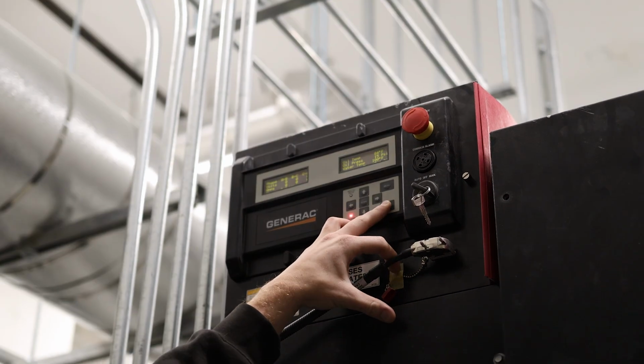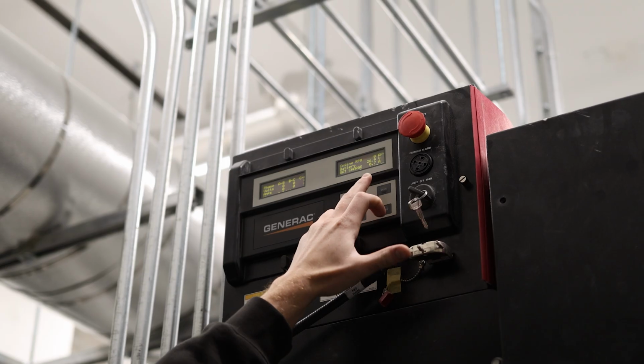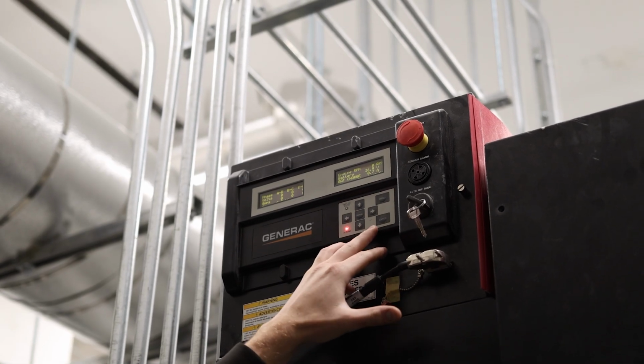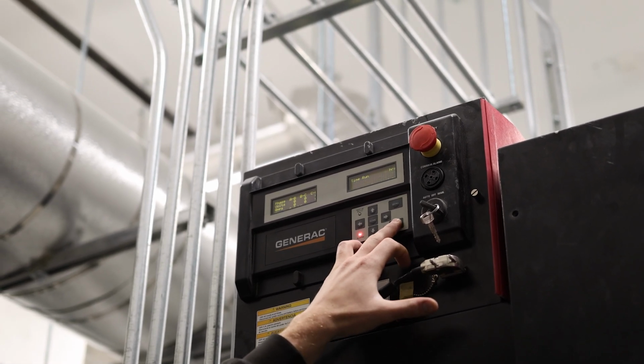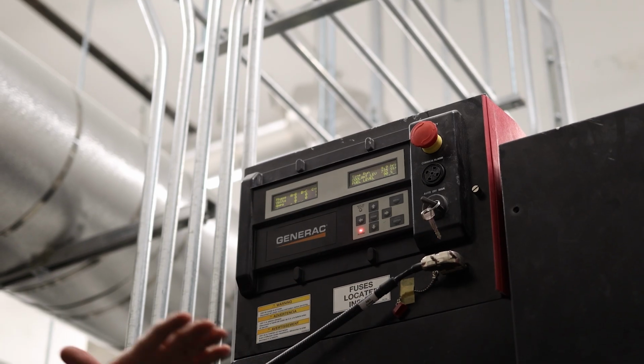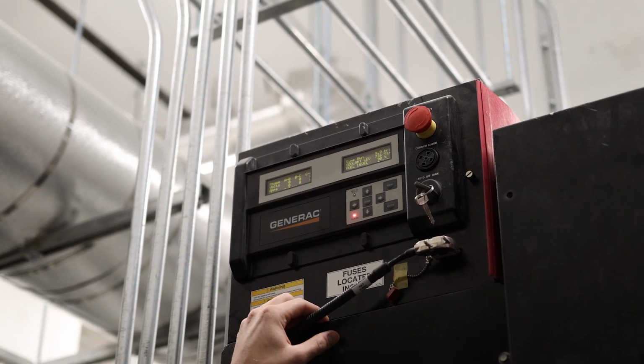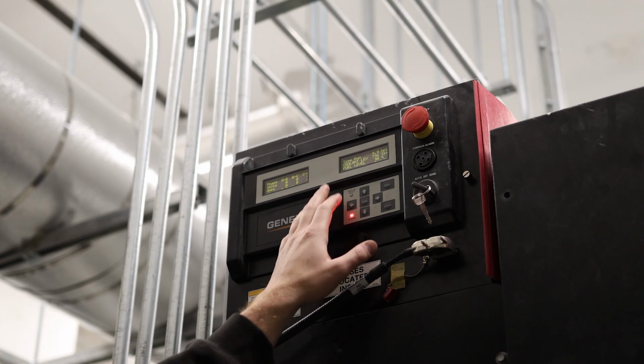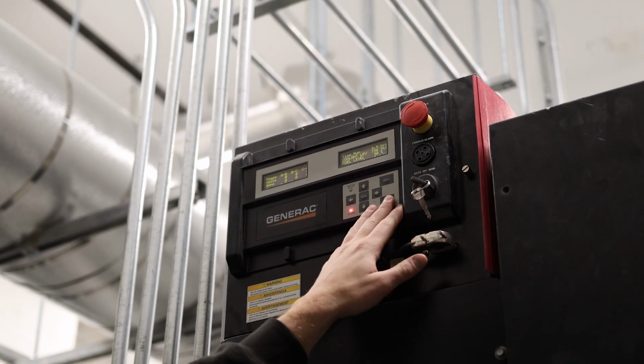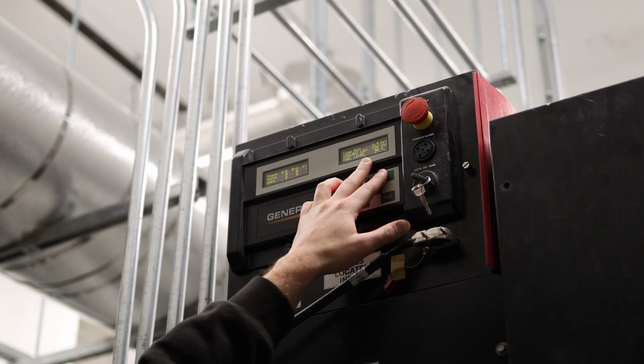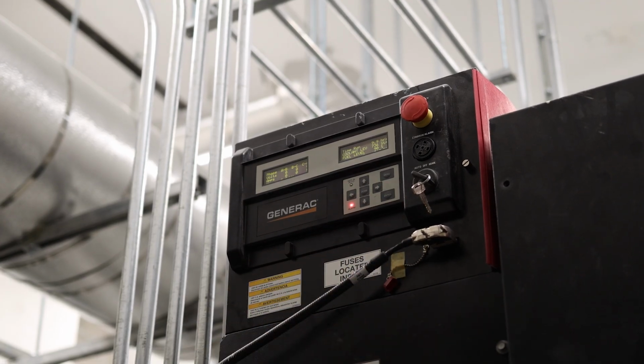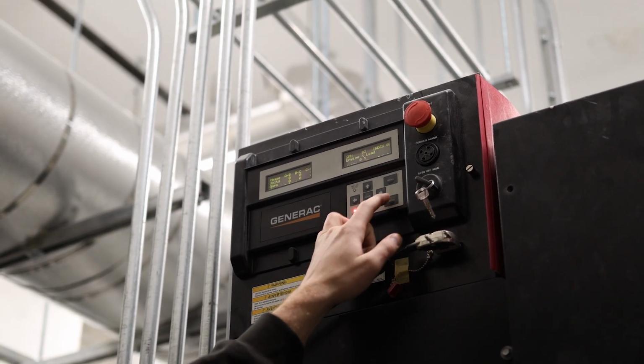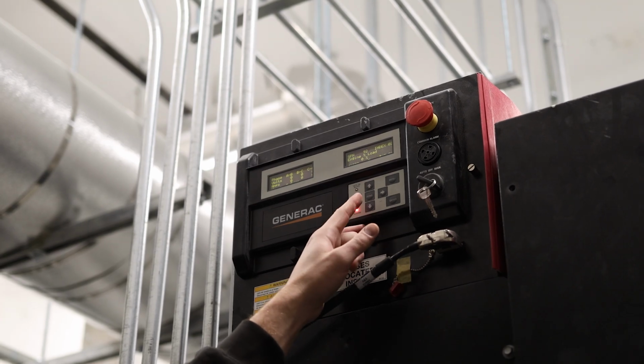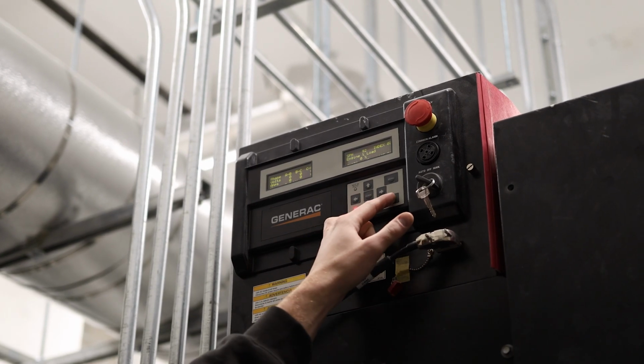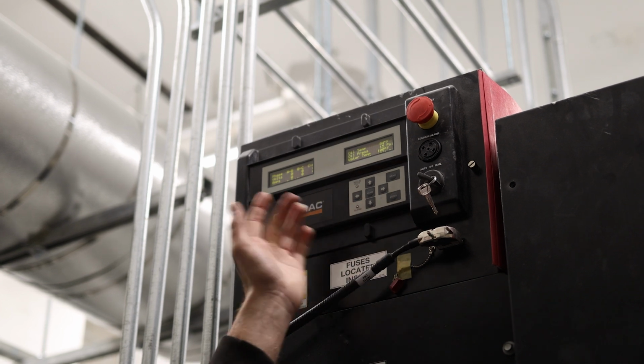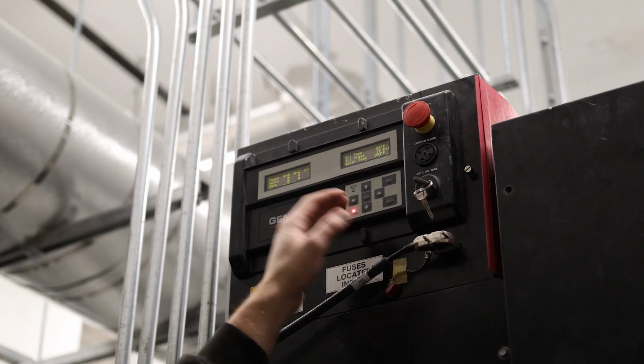This gives us a bit more details about our engine, including our battery charger output, our engine RPM. You can cycle through the pages by hitting enter. Each page holds three lines, and hit enter and it'll take you to the next page. This is how you can get your total run hours of the unit, currently just under 10. Our coolant level is monitored with that sensor, and it'll tell you our actual level, and then it'll eventually cycle through, show us our engine ECU fault codes if there were any, and once you're at the end, it'll go back to the start.